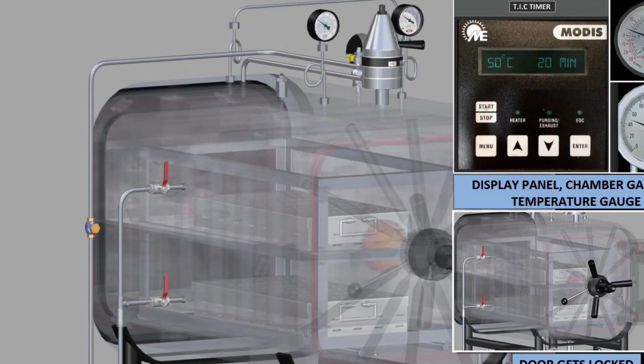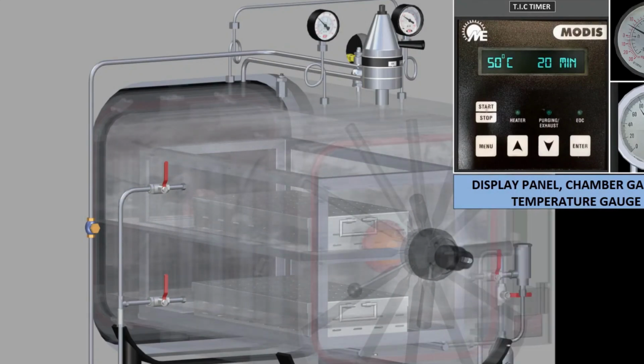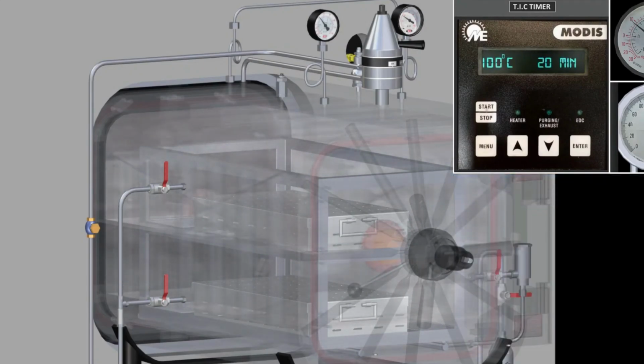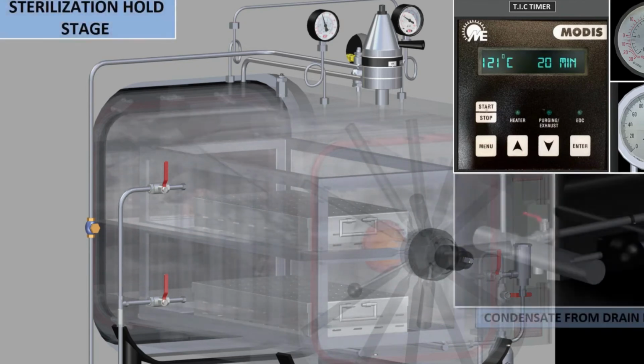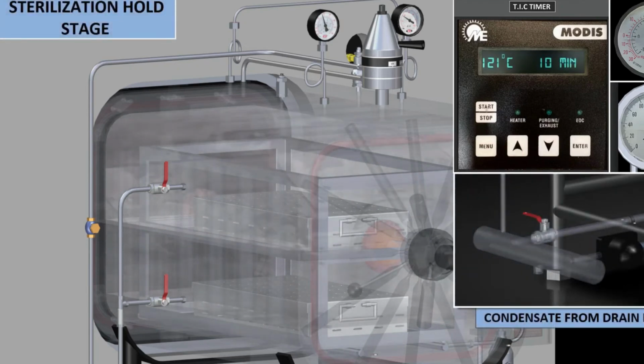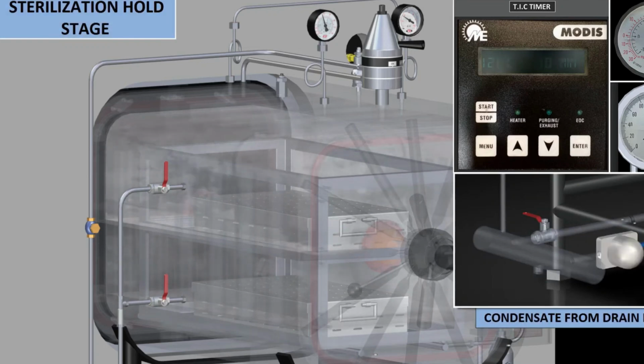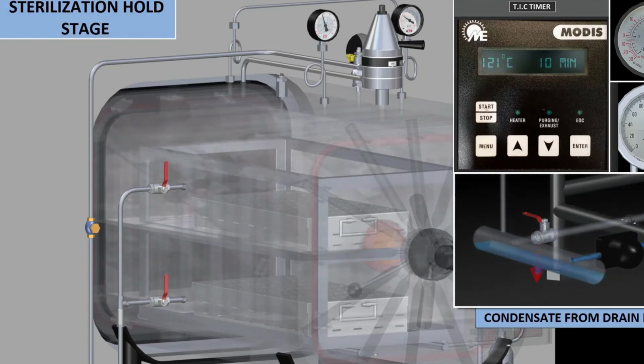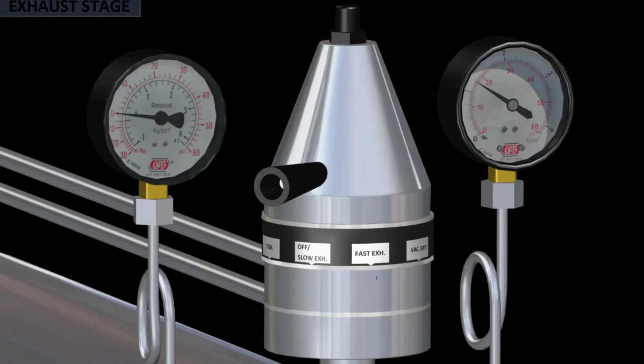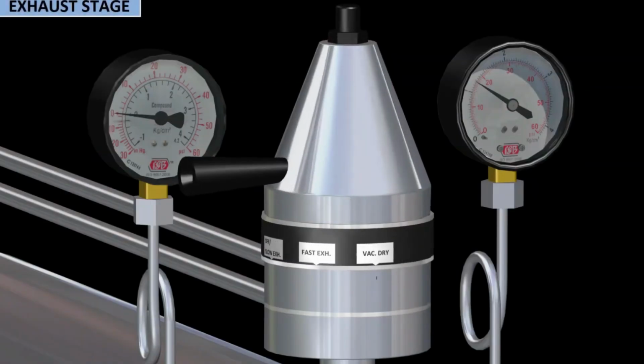Some sterilizers allow you to customize cycles based on temperature, time, and drying phases. Sterilization time depends on the load type, volume, and temperature settings. Exhaust and drying. Steam exhaust. After the sterilization hold time, the steam is gradually vented from the chamber, and pressure is released. Drying phase, optional. For wrapped items or certain loads, a vacuum or heated drying phase is often included to ensure the sterilized items are completely dry, preventing recontamination.